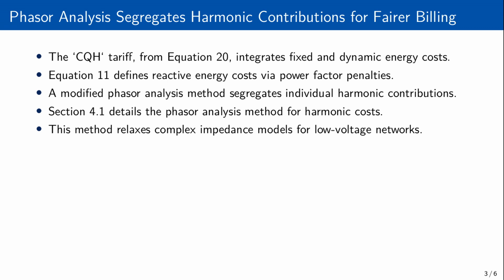Crucially, harmonic energy costs rely on a modified phasor analysis-based harmonic contribution method detailed in section 4.1. This method precisely segregates individual harmonic contributions from the utility, consumers, and prosumers, relaxing the need for complex impedance models typically required for such assessments in low voltage networks. This disaggregated approach ensures that penalties and incentives are assigned accurately based on actual power quality impact.